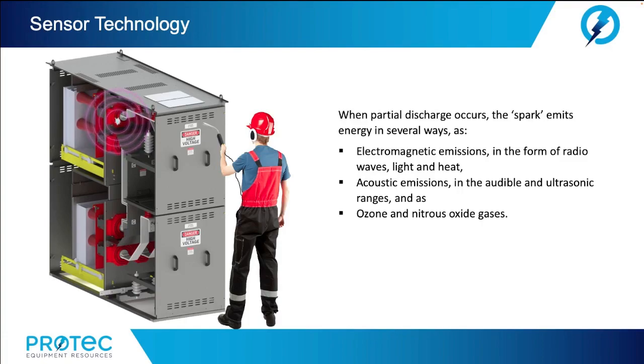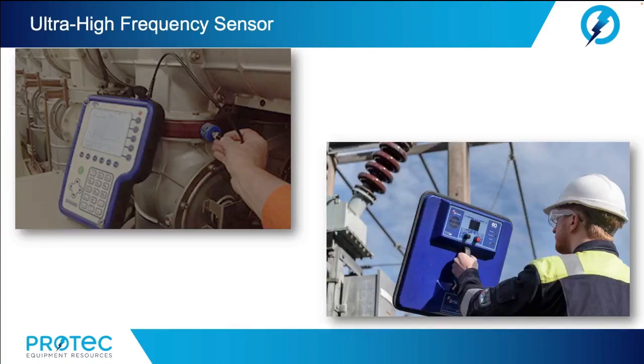Several discharge detection schemes and partial discharge measurement methods have been invented since the importance of partial discharge activity was realized early in the last century. The various detection methods and sensors provide a means of searching for partial discharge in a wide array of equipment and installation systems. The important item to remember is that there is not a one-size-fits-all solution to partial discharge testing. Using multiple sensing methods ensures that partial discharge activity is always discovered, localized, and characterized. So let's take a look at some of these sensing methods.